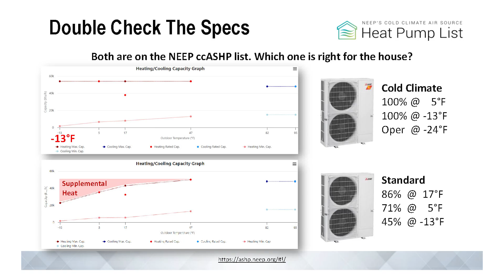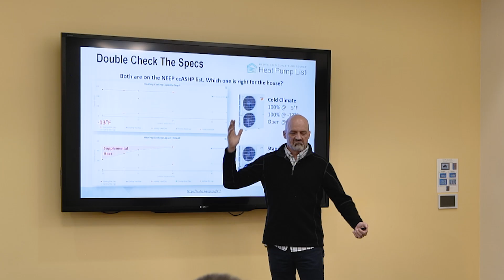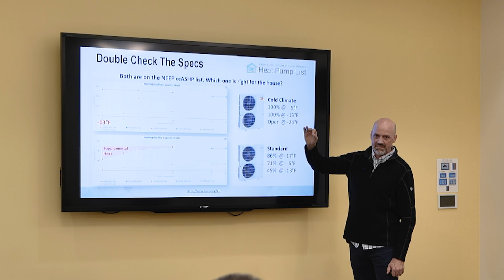Any other thoughts from the installer? That they turn off? No, this guy is guaranteed operation down to -24. This is the new 454B version. The -13 is just a tested number, that's why they talk about -13 by the way, same as -25 Celsius. It's just a number that the world tests equipment at, a number they picked. The operation guaranteed here is down to -24, and I've watched them operate at -29, -30.